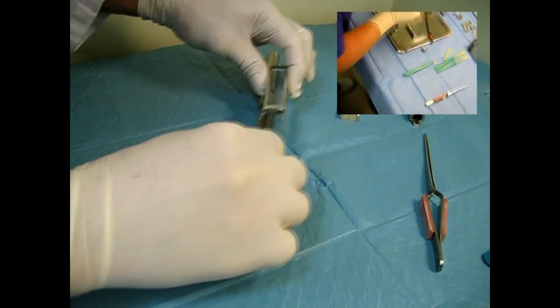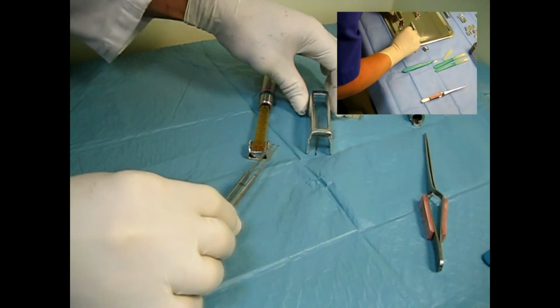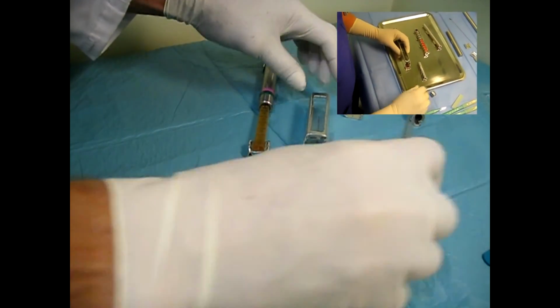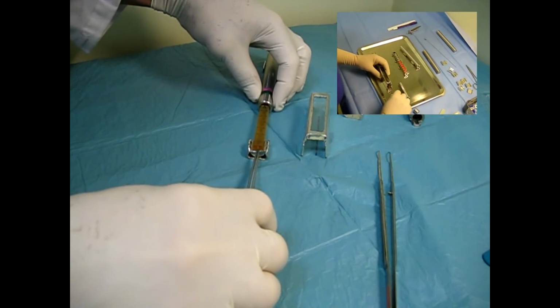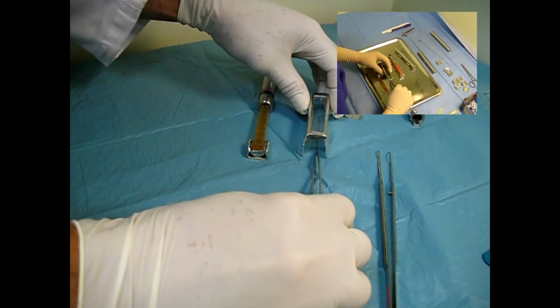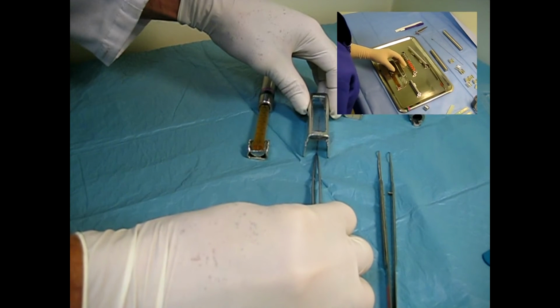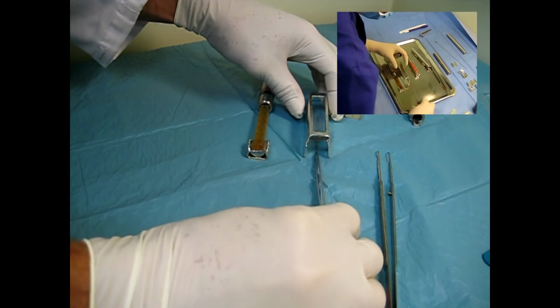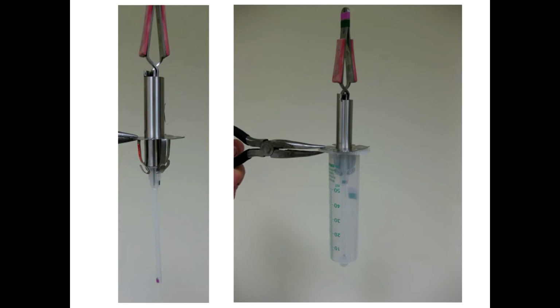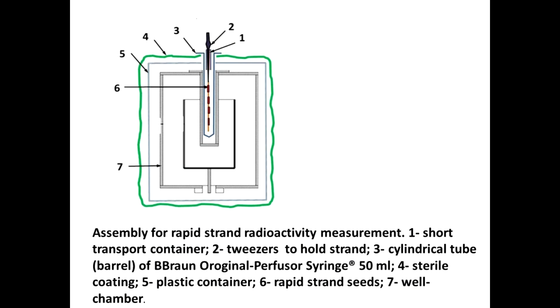Then we take the strands from the jig and together with shielded cover put to the table. For activity measurement we use another tweezers for more reliable holding strands end. Here you can see how looks like all assembled insertion into well chamber, keeping measured strand quite close to axis of well chamber to ensure acceptable reproducibility for results.